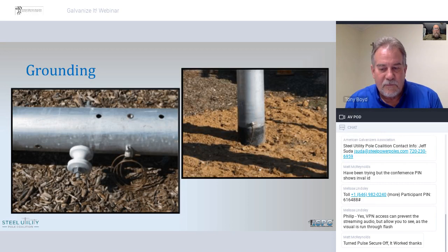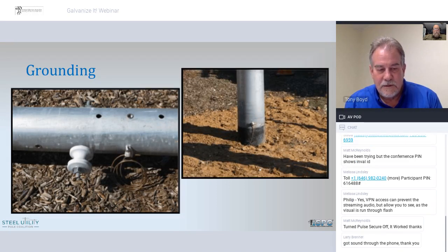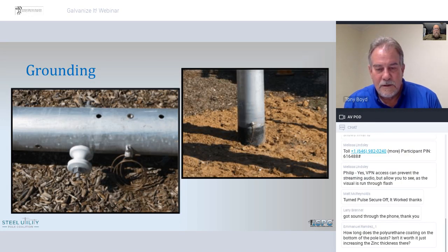And that might take a little bit of research or concern, and periodically, utilities should probably do some excavation at the foot of a pole once they go into steel and start to look to see if there is any deterioration of the coatings or deterioration of the steel. Coating with that dielectric corrosion protection eliminates that possibility. And then the other is the Corten. As far as I know, Corten poles have had very little reaction with copper that's in the ground.